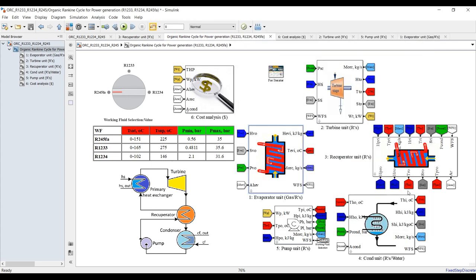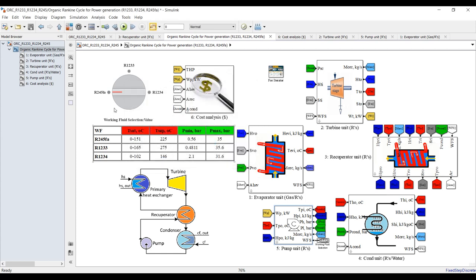Be aware that the condenser temperature should be less than the evaporator temperature, because of the cooling effect. For the pump, we just need the ambient reference temperature and pumping efficiency — around 0.70 to 0.75, no more. Save the model and hit Run to see the results.